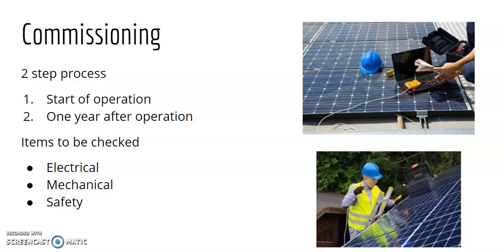Electrical items include checking that all disconnects are off when inspecting, the installation matches design documentation, all equipment is sized appropriately and is in compliance with the local authority having jurisdiction and the National Electric Code, making sure terminal connections are secure. Mechanical checklists are shorter comparatively and consist of making sure all the equipment is securely mounted, any roof penetrations are sealed, and the installation meets the manufacturer's specifications.